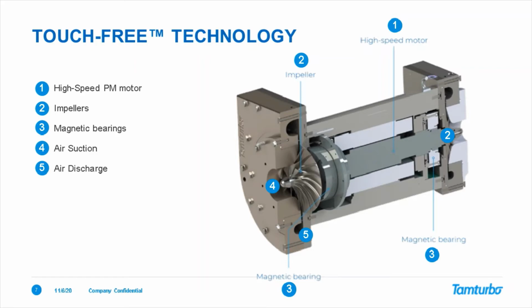And this whole package, the rotor and the impeller, is levitated in mid-air by so-called active magnetic bearings, which are measuring the position of the rotor at several tens of kilohertz frequency, so several tens of thousands of times per second, to the accuracy of micrometers. As it fluctuates in any direction from the center, it actively pulls it back into the center by using a current in a coil. So this keeps the very high-speed rotor typically at a 10 micrometer distance when it is rotating. And I will come back to it, but this technology has already been used for several decades.